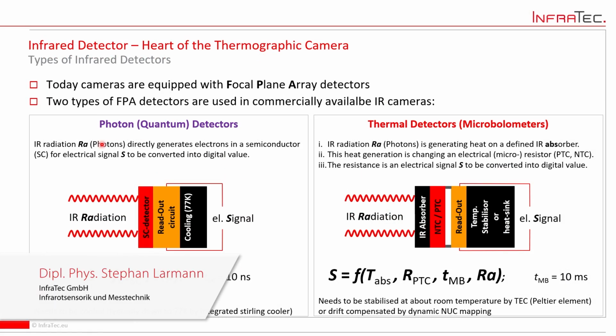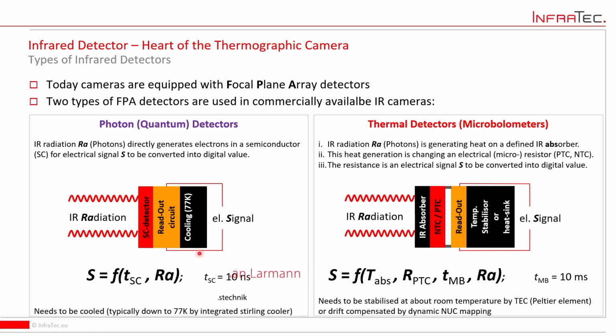There are two different types of detectors that work inside the camera, and they have very distinct features and performances. There are photon quantum detectors, often also called cooled detectors, or the cameras are then called cooled cameras. The way these work is the actual detector surface on each pixel is a semiconductor material. Think of this as one pixel. So if you have a camera with 640 by 480 or 512 pixels, then you have that number of individual sensors in that camera. Each pixel or each sensor pixel will give you one separate temperature reading.